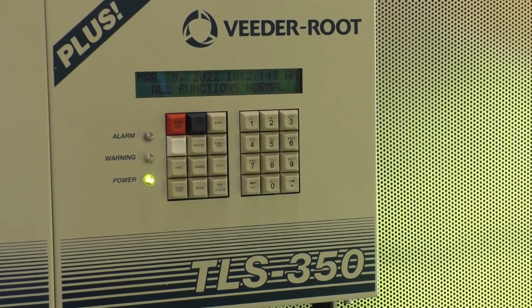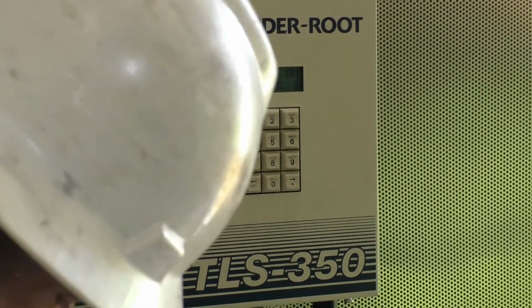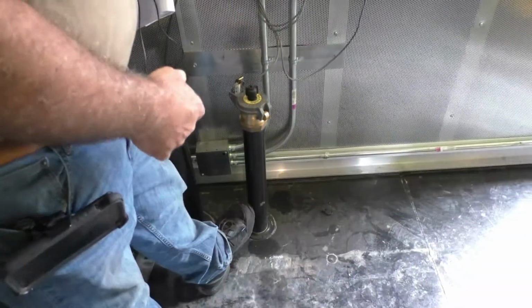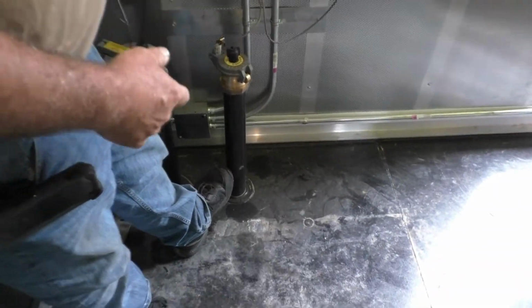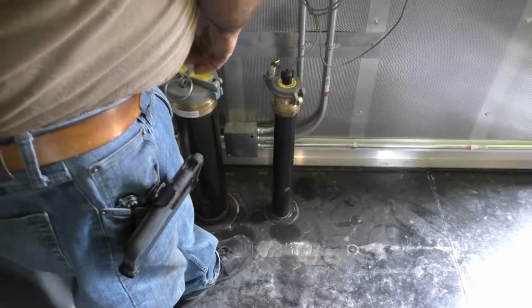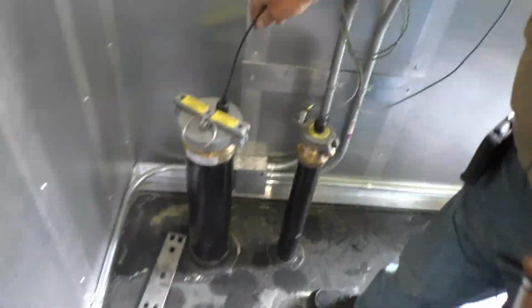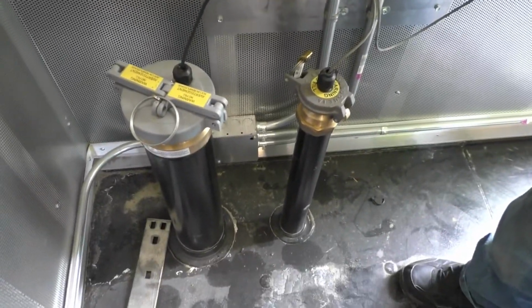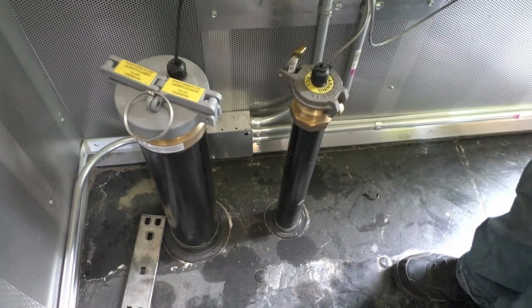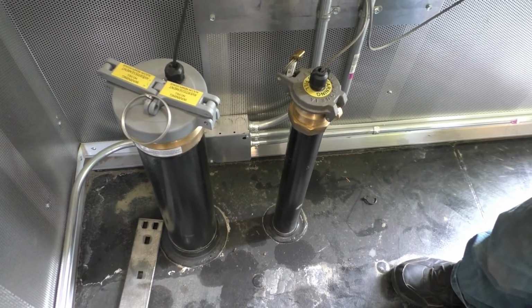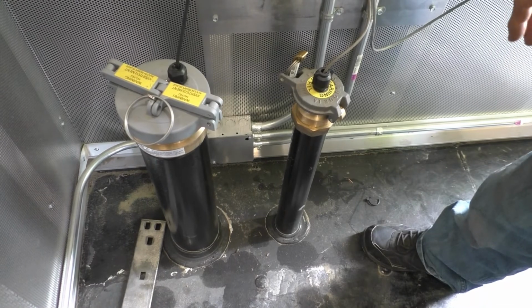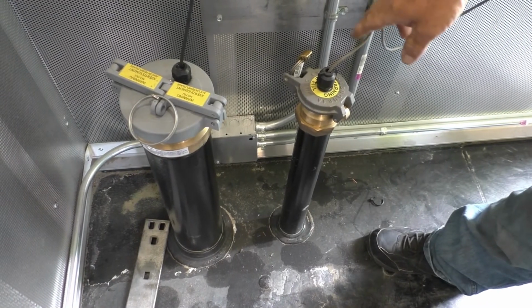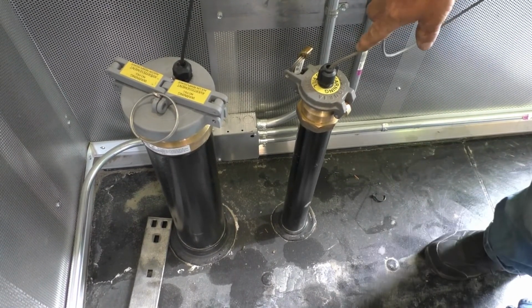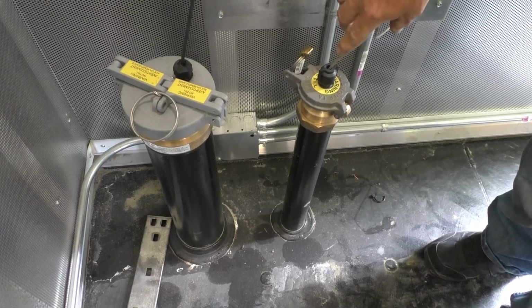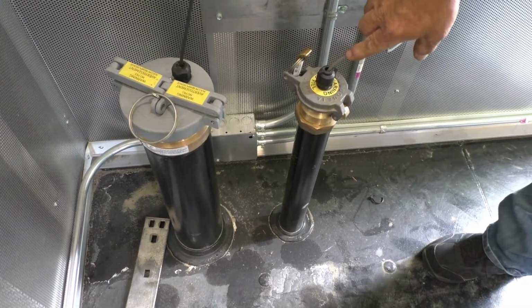It'll either be this sensor, which is going to be moved. I don't know where Fidelity's going to relocate it, but this is your probe. This is what tells you the level of the fuel. It gives your high level fuel warnings, low level fuel warnings, overfill and all that. This is your rupture basin sensor, which is right now in the wrong spot. Like I say, they'll relocate it.